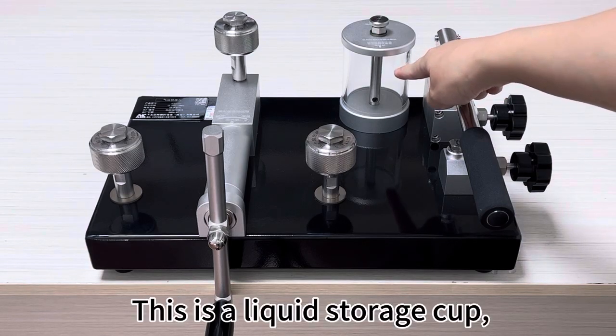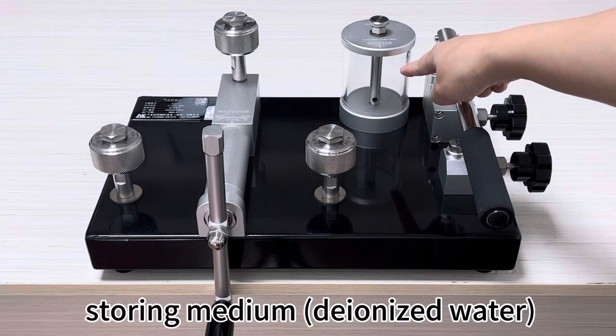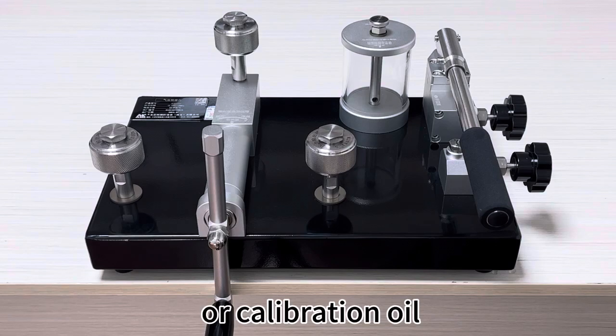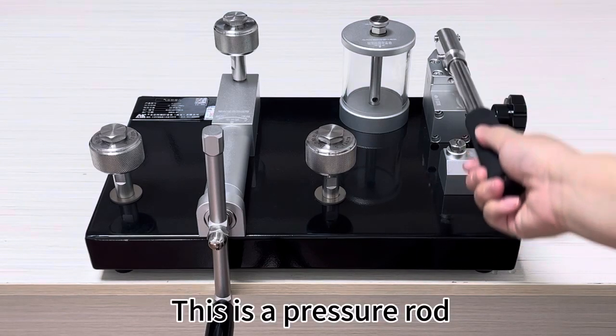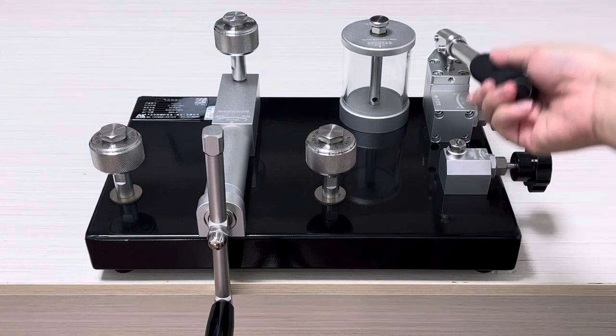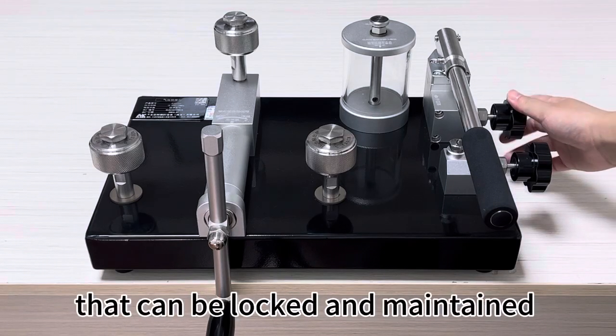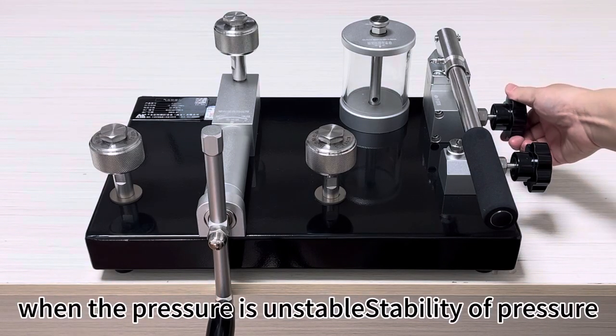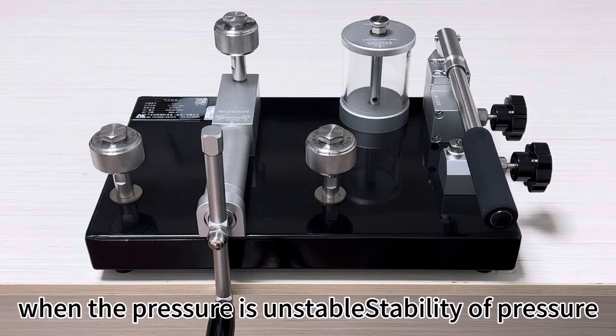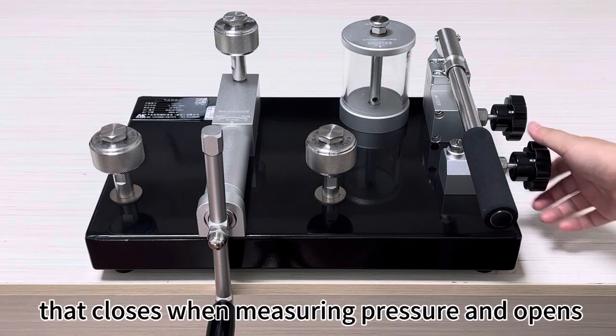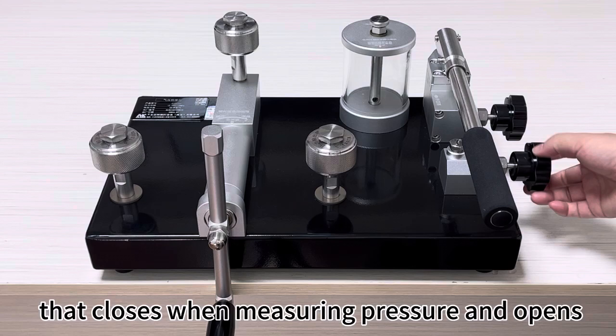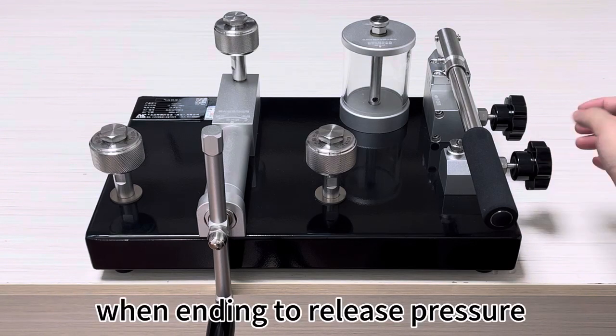This is a liquid storage cup, storing medium deionized water or calibration oil. This is a pressure rod that can easily create pressure. This is a shut-off valve that can be locked and maintained when the pressure is unstable. This is a pressure relief valve that closes when measuring pressure and opens when ending to release pressure.